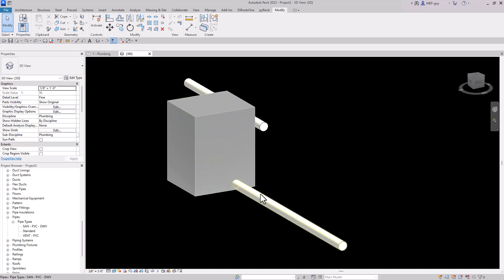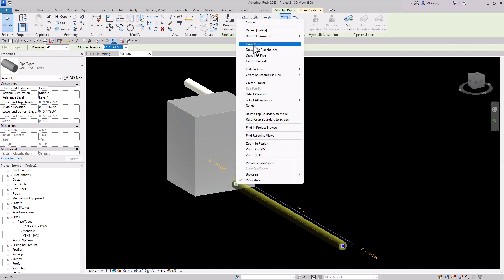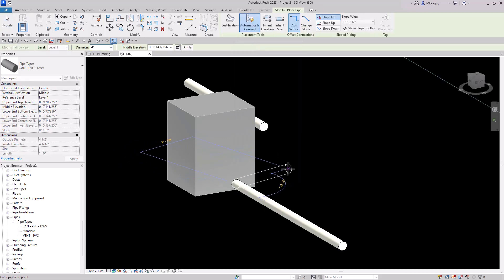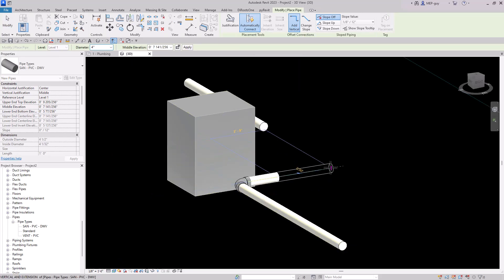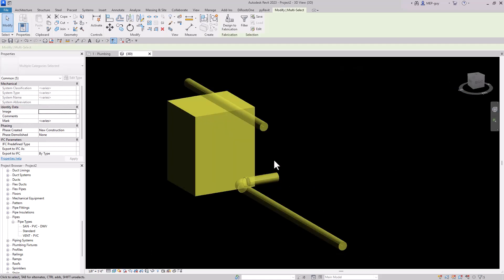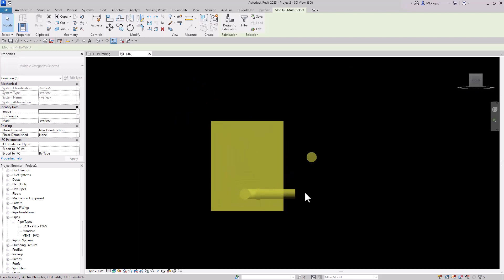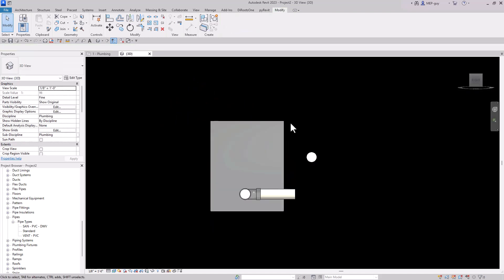So this is what I would recommend doing. Click on your pipe, right click on the grip, draw pipe, and I'm going to hold shift — it's going to lock this pipe to 90 degrees. I'll click a point right there. Once I have that, I can select all of my elements, and when I hit the view cube up here and click 'Right,' it will automatically center this into my view. This is kind of like a section view and I can work just like I would in a section.